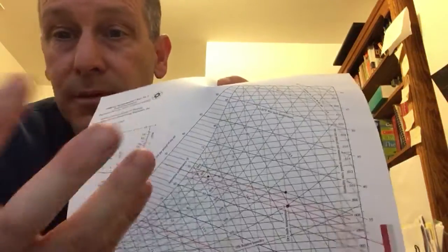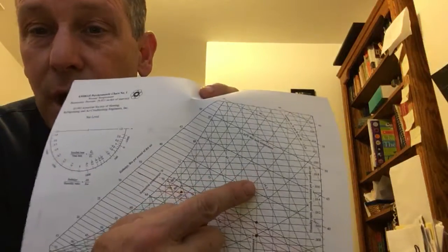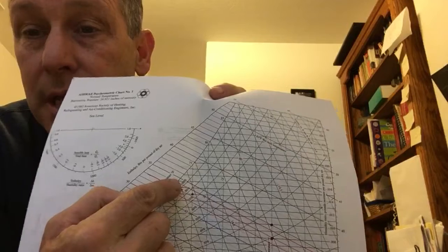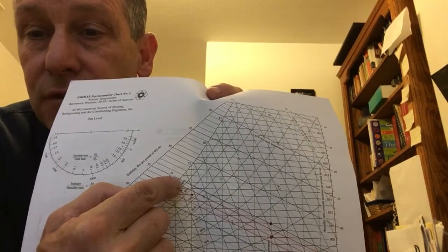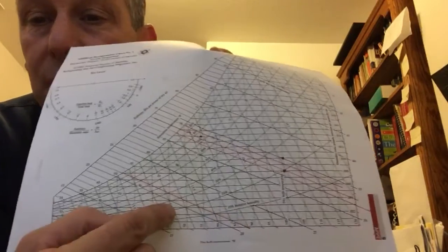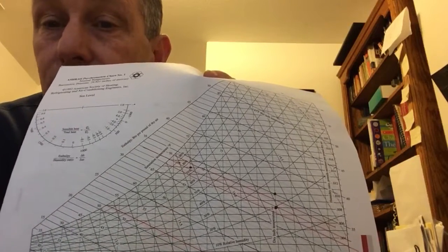So for any sample of air, to figure out its dew point, plot it on the psych chart, and then imagine a process where it's cooled without moisture addition or removal, and when you hit the saturation curve right there, you've reached the point of dew formation. Then you just read straight down and get what the dry bulb temperature is at that point, and that is called the dew point temperature.